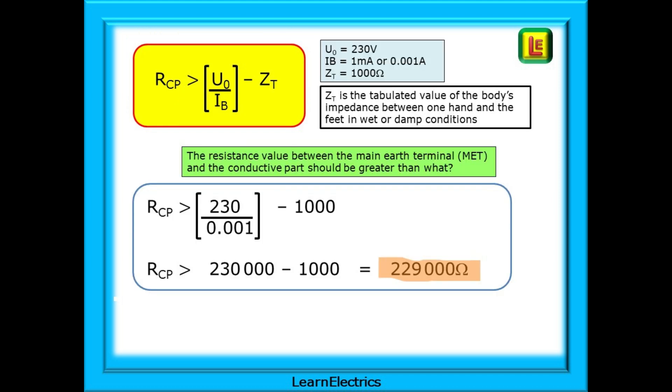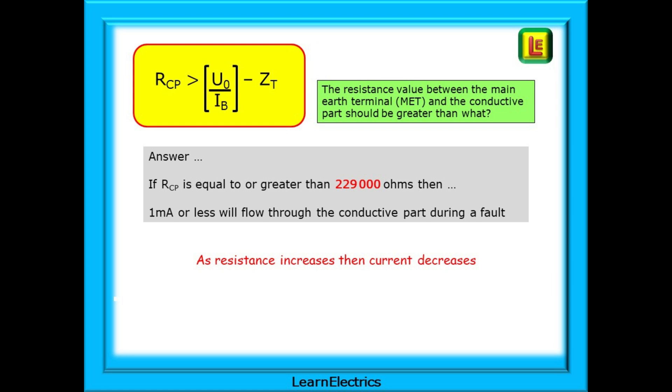Here's the formula, and to the right is the information that we know. Again, this is Ohm's law. We have a voltage, a current, and a resistance. So let's answer the question. For not more than 1 milliamp to flow, the resistance value between the main earth terminal and the conductive part should be greater than what. Pause the video and follow the calculation through, breaking it down into nice easy steps. Done correctly, the answer should be 229,000 Ohms. And calculating the answer is as easy as that. If RCP is equal to or greater than 229,000 Ohms, then 1 milliamp or less will flow through the conductive part during a fault. And if the resistance increases, the current will decrease further.